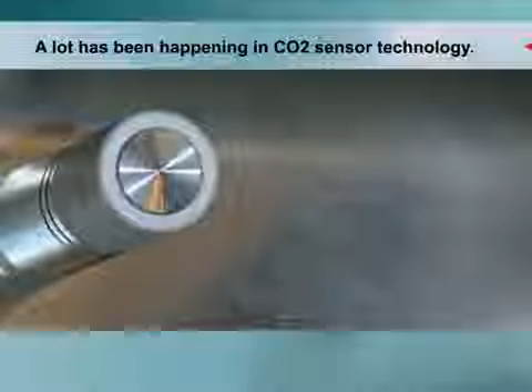The infrared measuring system monitors the culture parameter CO2 and regulates it highly selectively. It does so independently of humidity, in contrast to other measuring systems. Interference from other gas components is not possible. The original CO2 level is restored within 6 minutes of opening the door. This is essential for the stabilization of buffer solution pH and thus for reproducible culture quality.